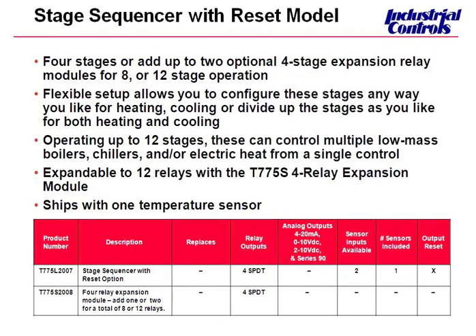In addition to the P, we have what we call our sequencer model — the T775L — also used for staging multiple boilers and multiple chillers. This time you can have two control loops instead of just one as you get with the T775P. This model is also expandable up to 12 relays using the T775S expansion module, and it's also available with reset. Pretty impressive.